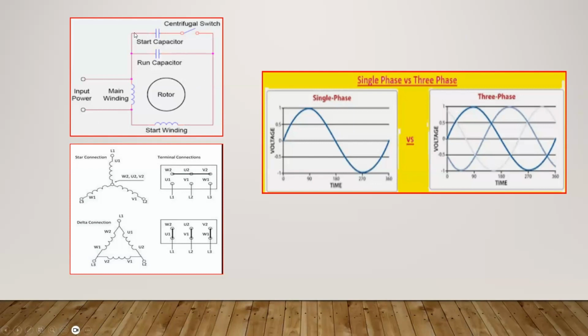So there is an advantage to using 3-phase motors on the efficiency. Some of the newer high-efficiency motors, on a smaller machine, can be about 85 to 90% efficient. On a bigger machine, they can be as high as 95% efficient. So what we're talking about here is the two different types of motors that exist in the marketplace. In most applications, this covers about 90% of the world's market. There are also servo motors, switched reluctance, multiple other types, but the main workhorse of industry is the three-phase induction motor.